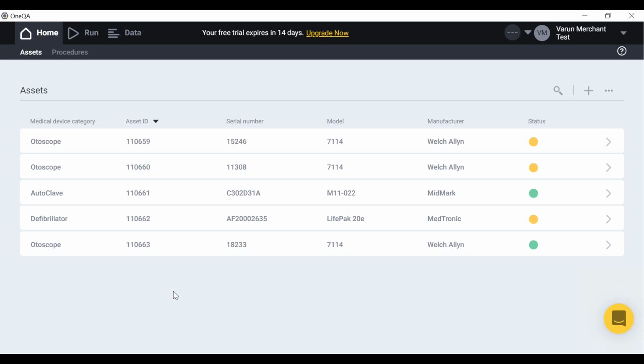Yeah, they already have their PDF. Things, like we said, we set it for 50, 100, 200, right? And then you move on to the advisor and start the back and forth. Does it load up to their format? Yeah, so your typical clean flow, what we hear for a universal wish, is that it goes to that automated test, done, and then right off to the CMMS, seamlessly. It could be a 1 stage, it could be a 2 stage, depending on verification, whatever you need. The level of integration is essentially twofold. You have the basics where we can pull in the asset and the procedure information into OneQA, run the test, generate a report, and push that report back to the CMMS system. Then there are a few customers we're working with who require a deeper level of integration, so we work one-on-one depending on the need.